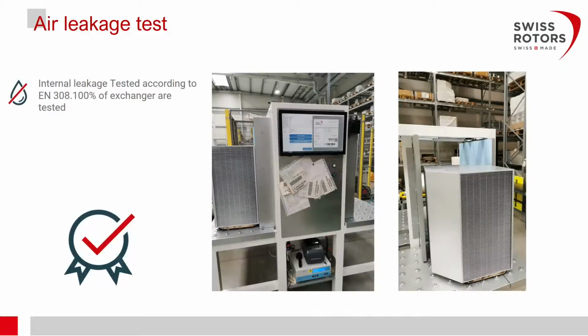And the tolerance, generally speaking, everybody can get this norm and read what is going on with this internal leakage test. But generally speaking, via the nominal flow through the exchanger, there cannot be higher than 0.5% of leakage. And we have a special design, as on the pictures on the left side and the right side, you can see that there is a suction and pumping small fans, and we are checking the difference between one side and the other side.